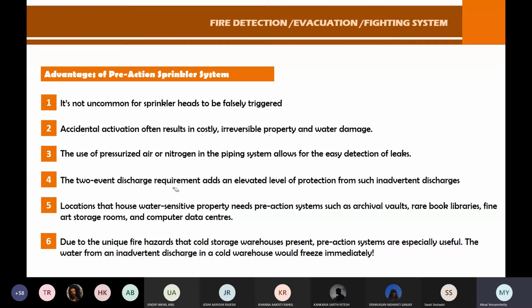Second thing, how will we know on which floor this leak is, BMS? Because whatever sprinkler connection you have, everything is zoned. Where the pressure drops, where the air pressure drop happened, those sensors are again linked to your BMS. Otherwise BMS would keep searching. In a 60-floor building, you wouldn't know which floor has fire, or who made the mistake.